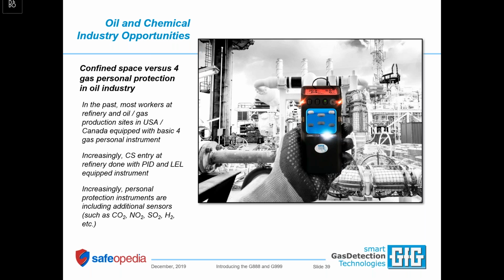You can do that with the 888, and you can also do that with the 999. With the 999, we have the additional availability of power-hungry sensors like the PID. So if you want a comfortably worn personal protective instrument, 5-gas with PID, with the 999 you've got it. You can have the pump or leave the pump out — it's an option, just like wireless, you can add it or leave it out.